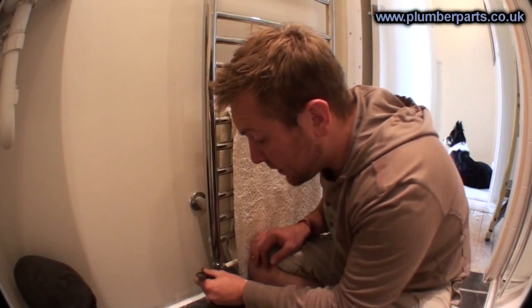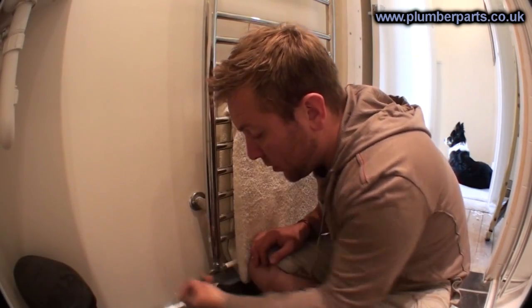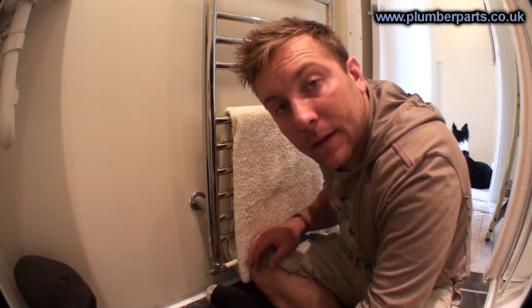Once it's fully closed, just slack it back a quarter of a turn. Do that to each radiator upstairs, and you should find then that the radiator side of the heating system is balanced.